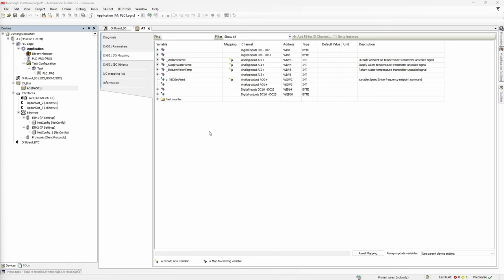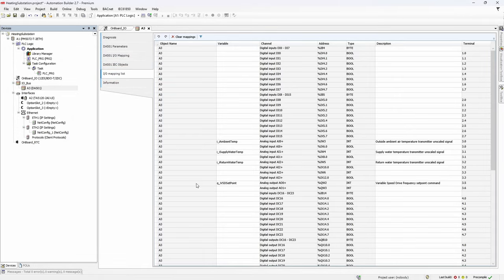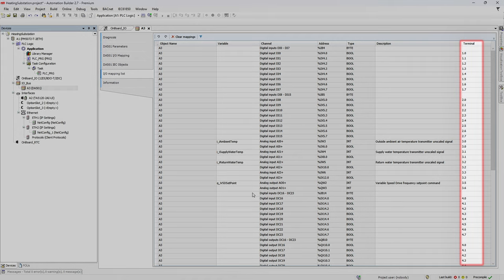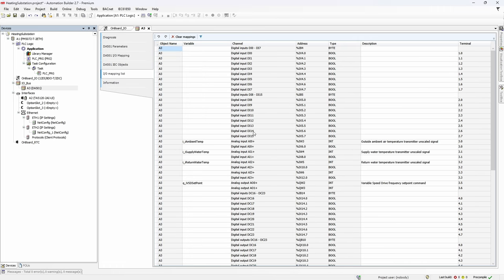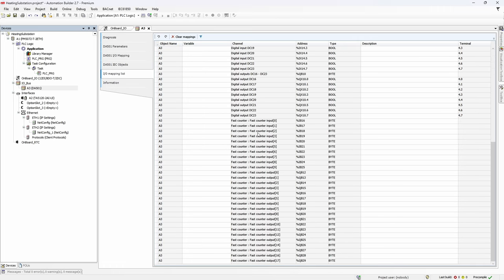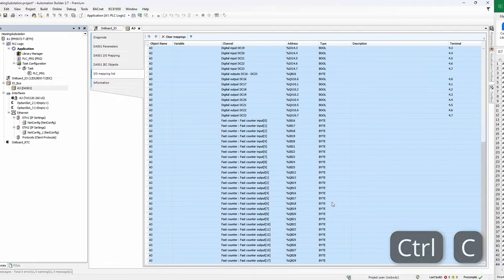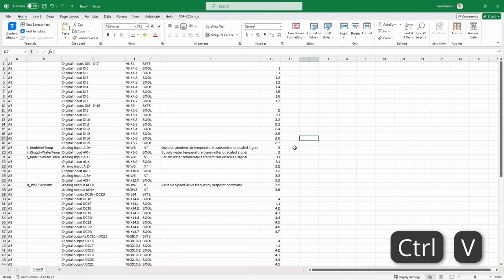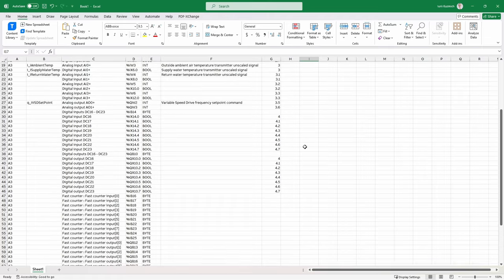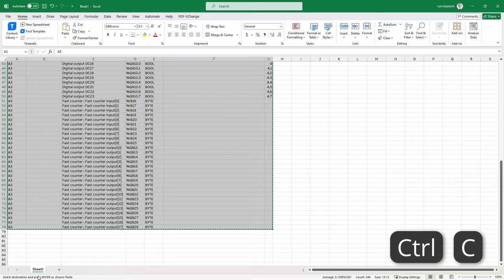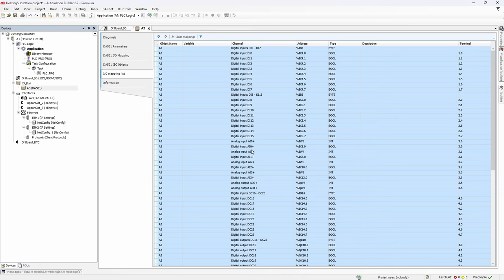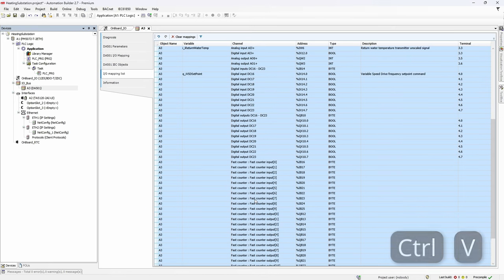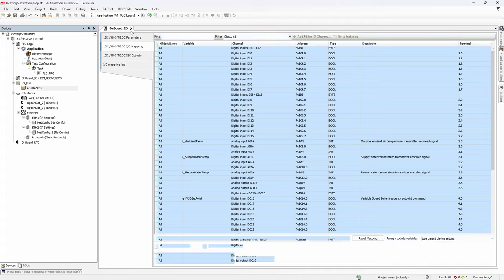There's one trick which somehow makes IO mapping process less tedious. For every IO module there is a tab called IO mapping list which gives you pretty much the same information as before except maybe terminal column, but in a flat table form. And the cool part is you can select everything, copy it, and then paste it into a spreadsheet. Even cooler is that it works in the reverse as well. You can copy the table in the Excel window and then paste it into Automation Builder with all the channel mappings and descriptions. And even that is not all.